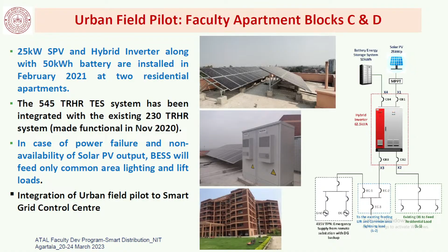Now, one very interesting thing—do we have time? Thermal energy storage—I don't know if you've heard of this. It's very good for city areas or tall buildings where air conditioning load is very high. In fact, a survey showed that almost 44% of the load is air conditioning load. This creates a lot of problems and is increasing day by day. So the question is how to reduce the peak demand that comes in the daytime due to large air conditioning load—this is another viable option. It's not electrically connected, but thermally connected. It contains a tank filled with glycol solution, and this building already had an air conditioning system with a 75 ton chiller, with a total peak load requirement of 150 ton.